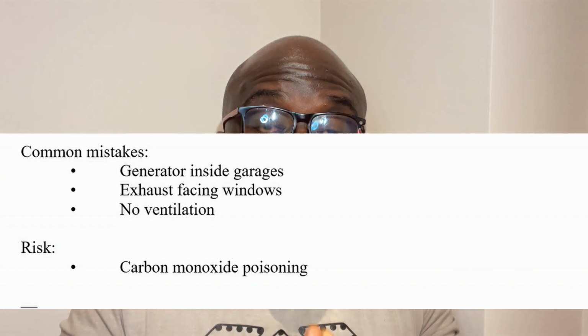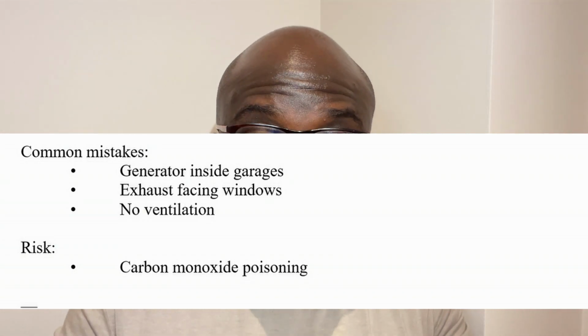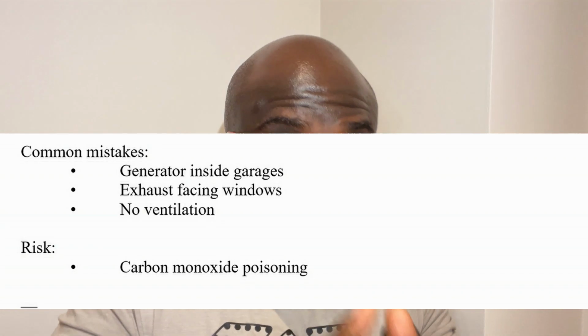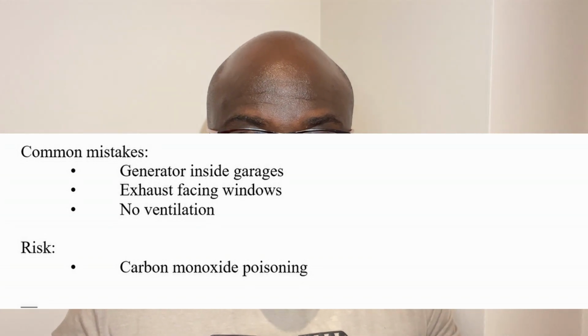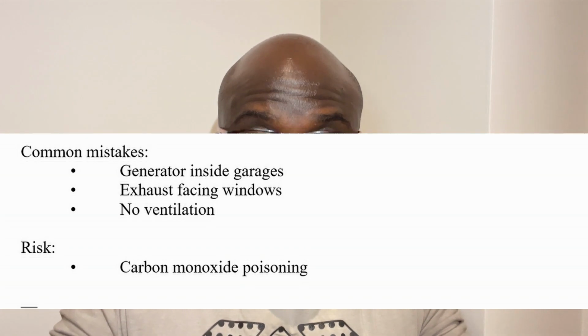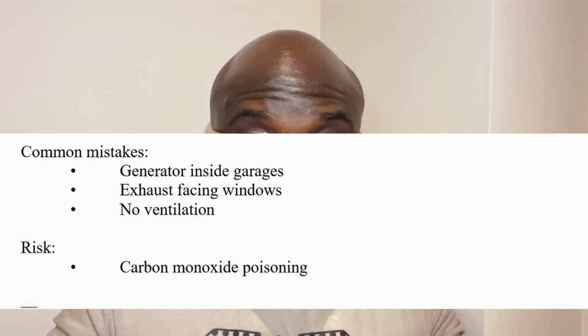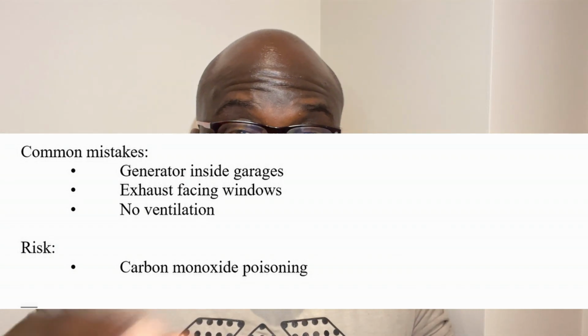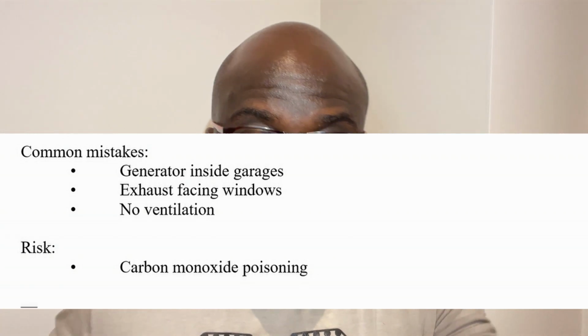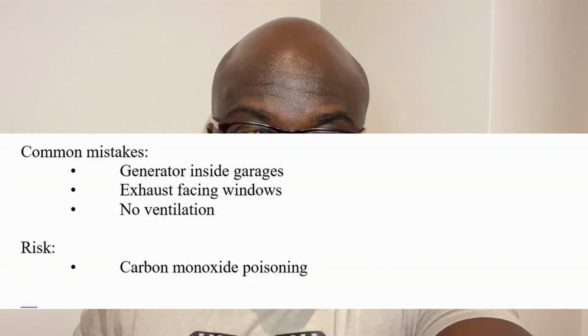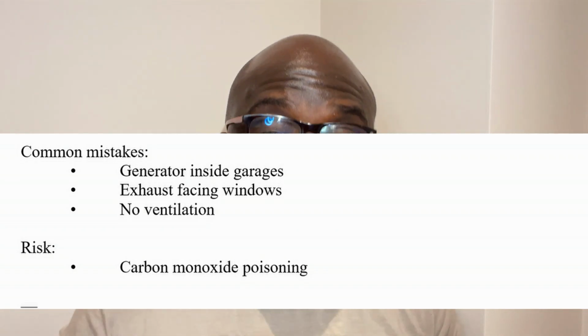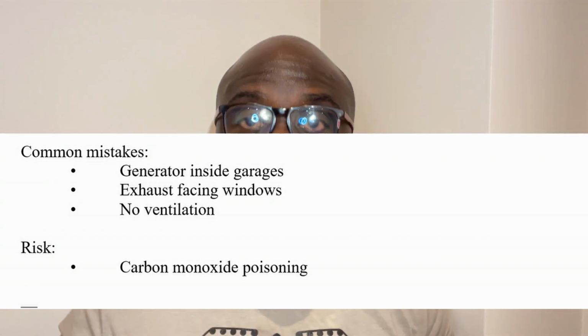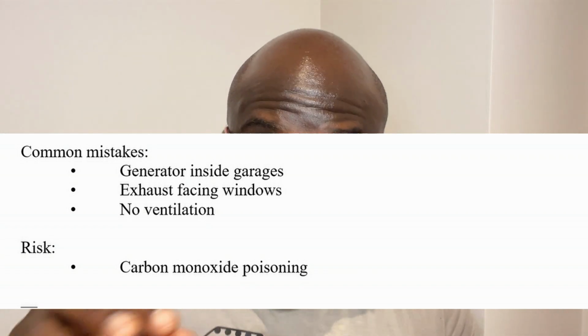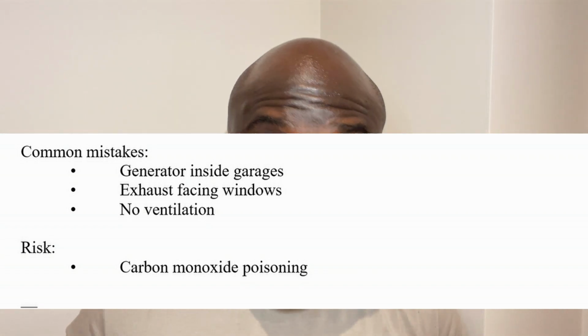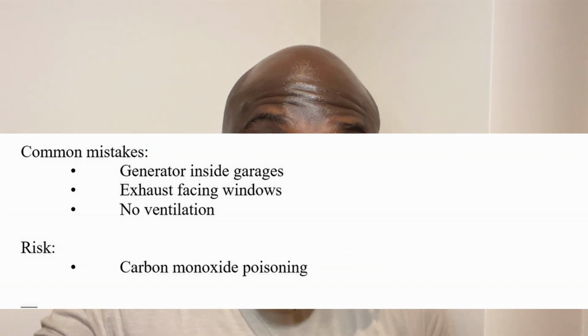I would not even recommend that you install a generator inside a garage. Don't install a generator inside a garage. A common mistake is the generator exhaust is facing the window. Make sure the generator exhaust is not facing the window, because that means it will exhaust into the home. Another common mistake is that there's no ventilation. What is the risk? Carbon monoxide poisoning. Remember, carbon monoxide, you can't see it. I think it's odorless as well. You can't smell it. It's a slow poison.